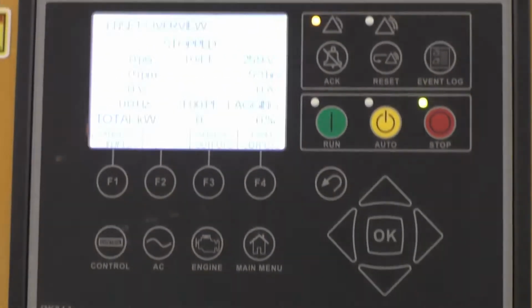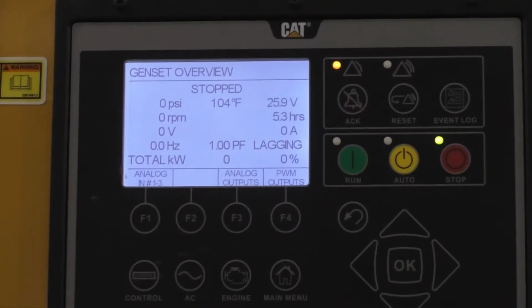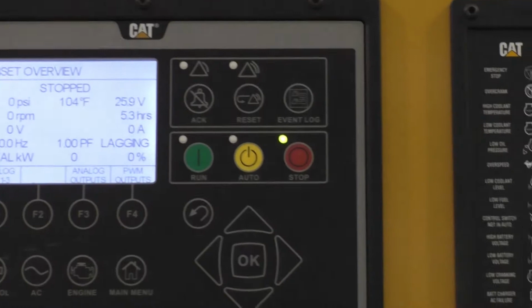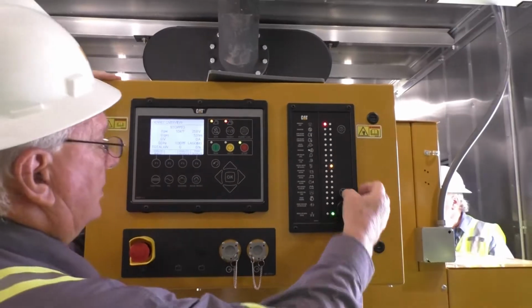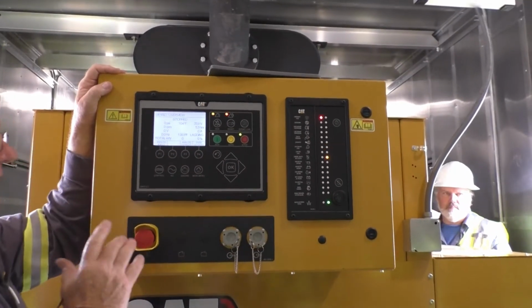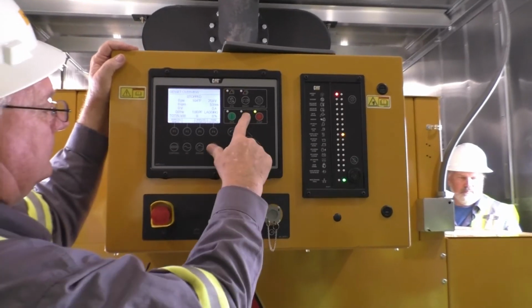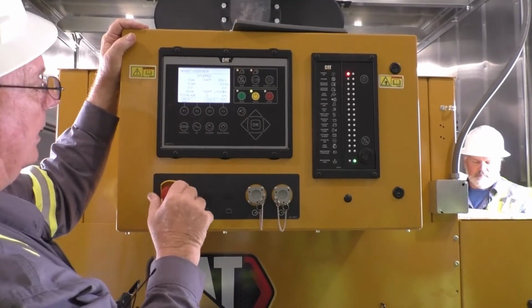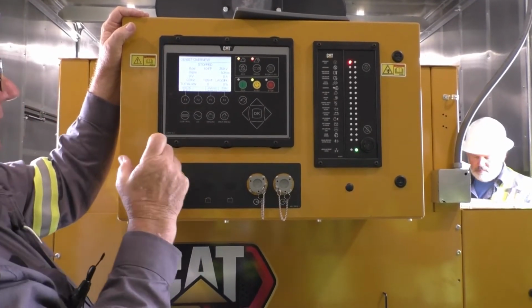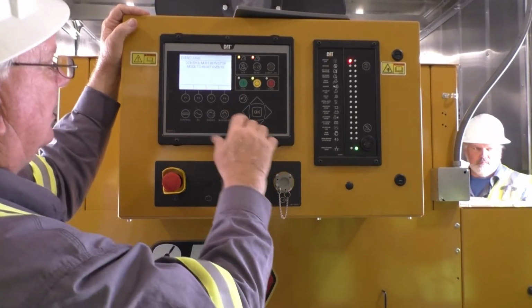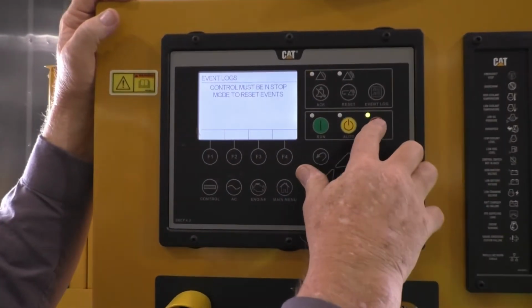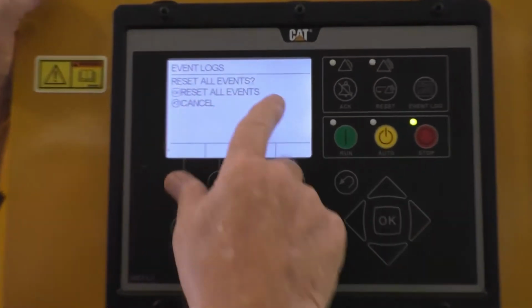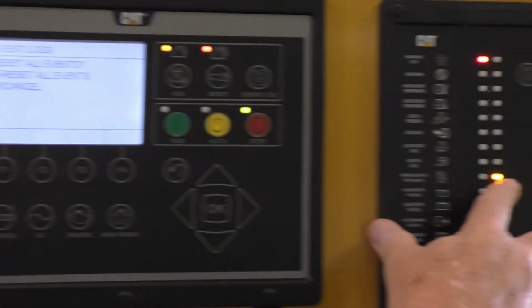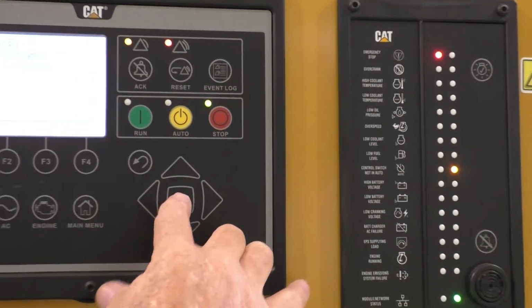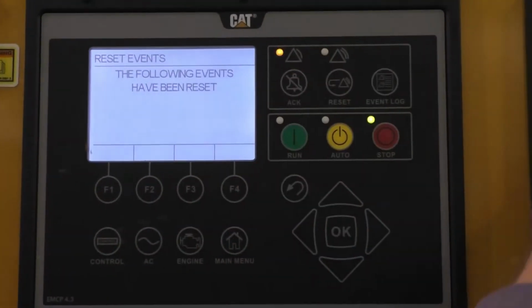So, any questions on this? All right, we're going to hit this and set it off. Now we're going to get that. You can silence that. Now, say we're in auto. Now we want to reset this. You just twist it, it pops out, and you hit the reset button. It's going to give you this. You have to be in stop. So it's going to say reset all events. Now we went out of auto back to not in auto. Hit that, loses the red.